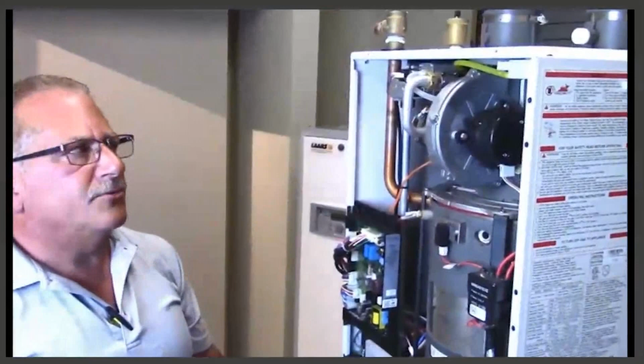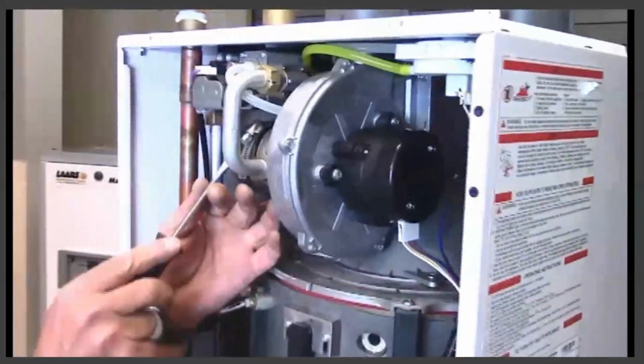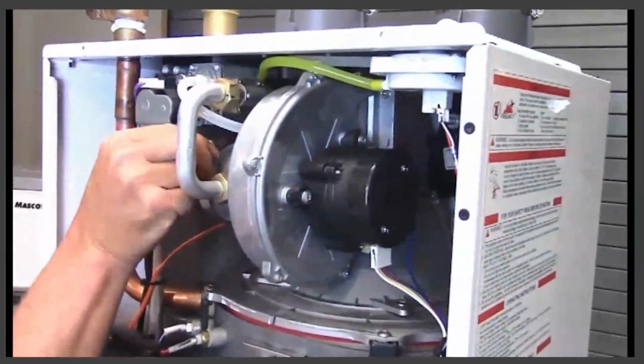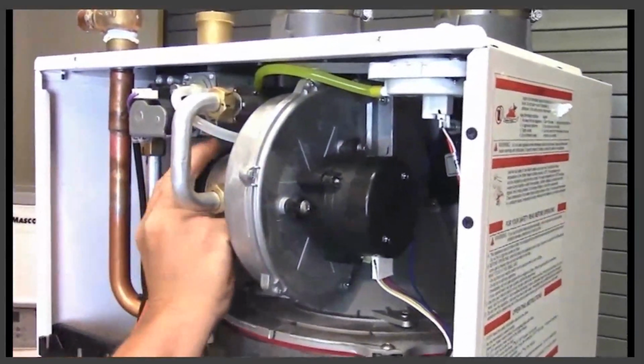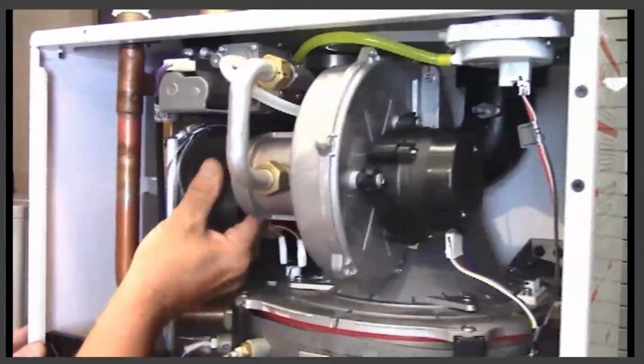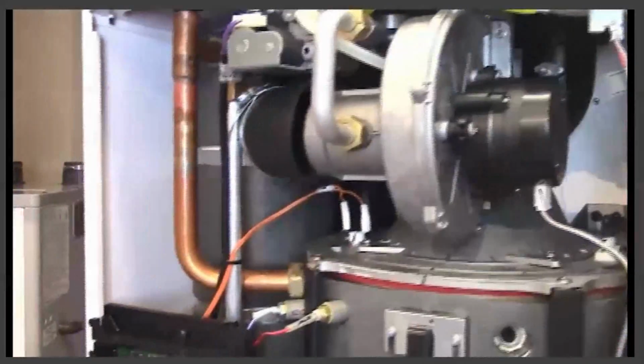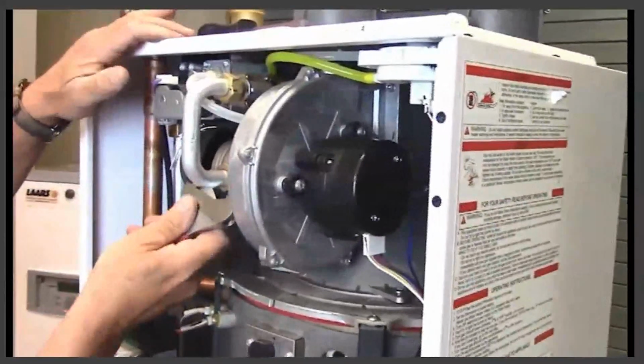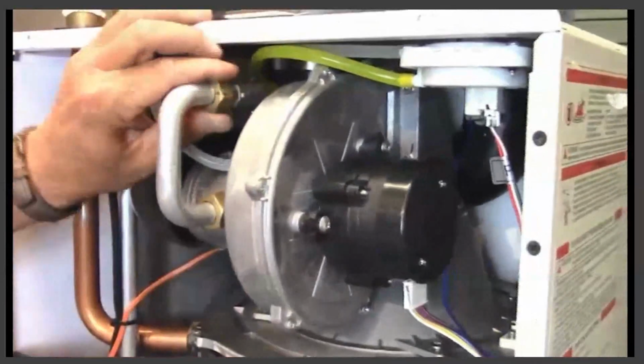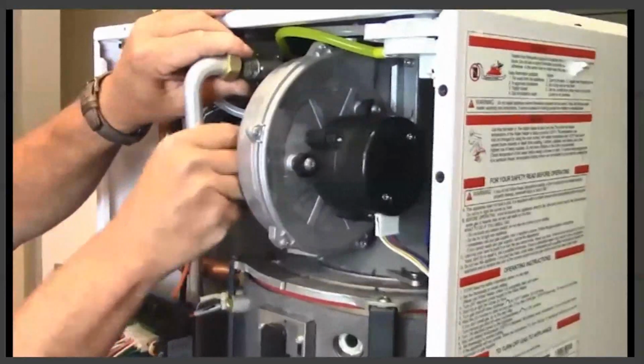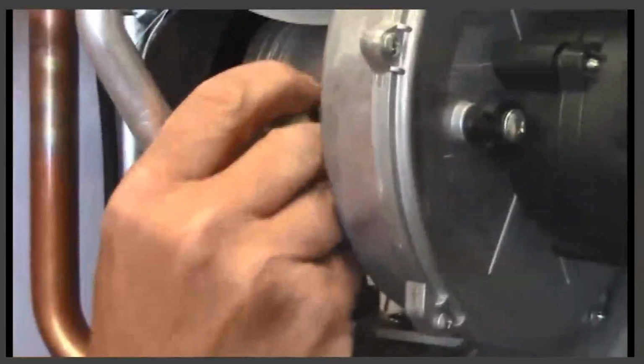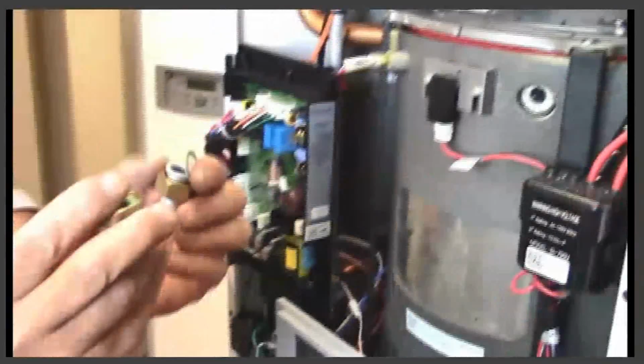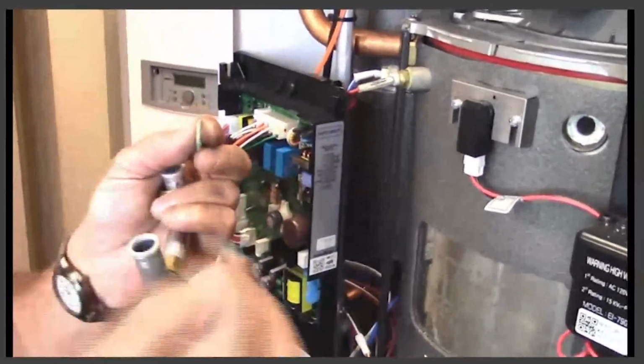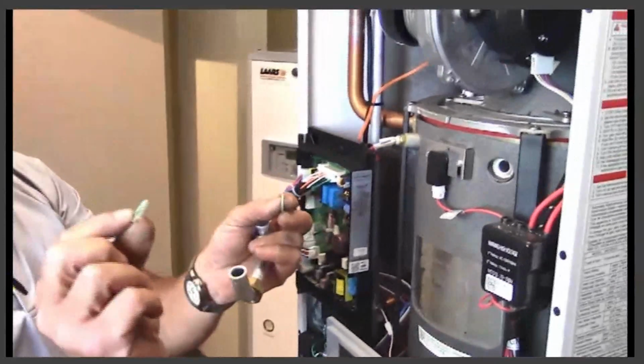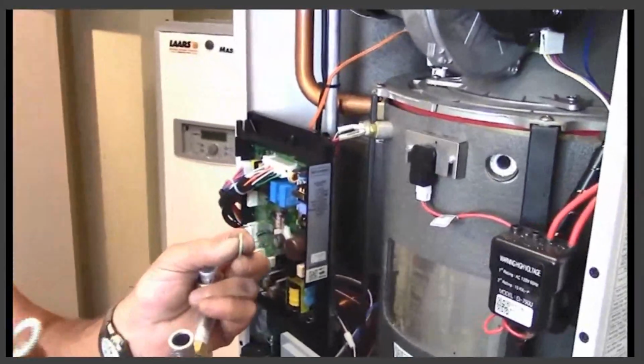Removal of the blower assembly requires removal of the fresh air inlet boot. That's held on with a clamp. You can slide that clamp down the rubber boot and remove that boot and get it out of your way. Removal of the gas train is also necessary. Underneath that aluminum tubing of the gas train, you're going to find 2 cardboard gaskets. Orientation of those gaskets is not important. They can go either way. Replacement of those gaskets is necessary after inspection if you see that they're cut or torn or spread.